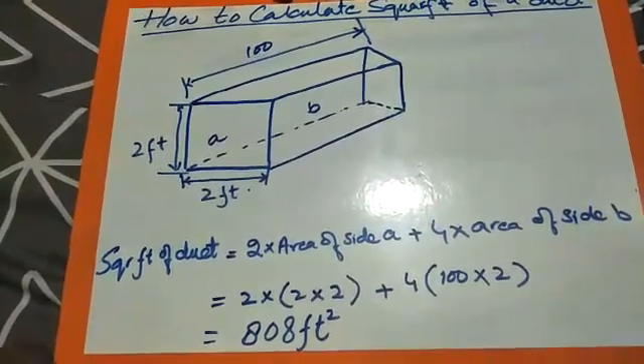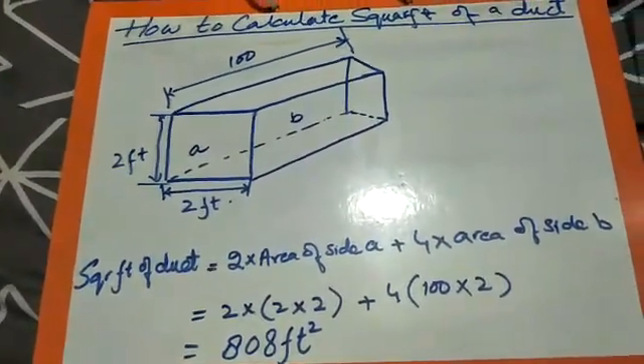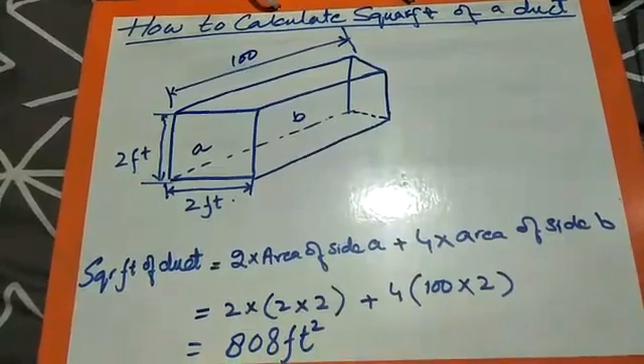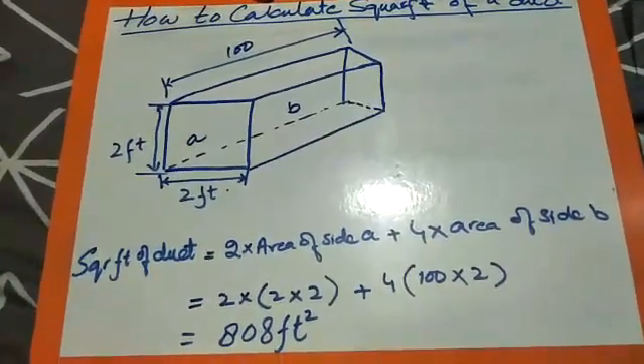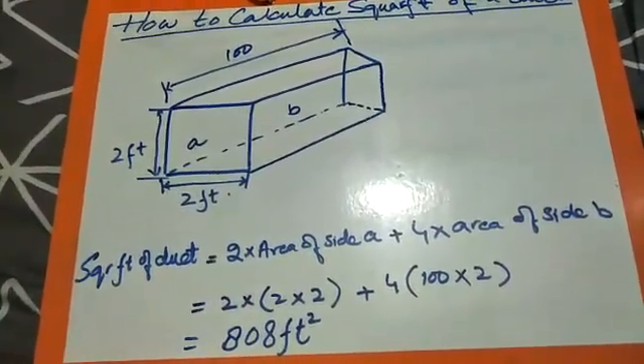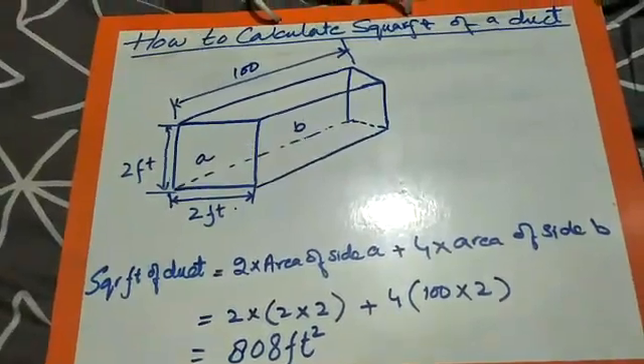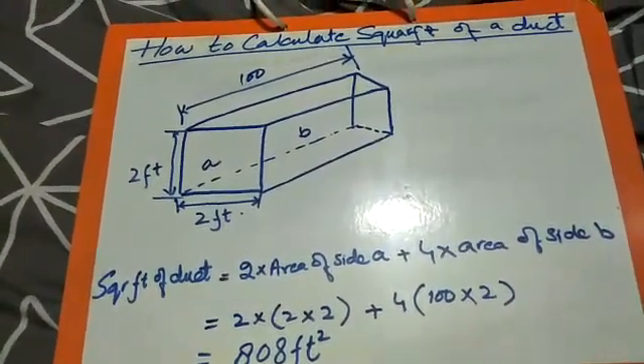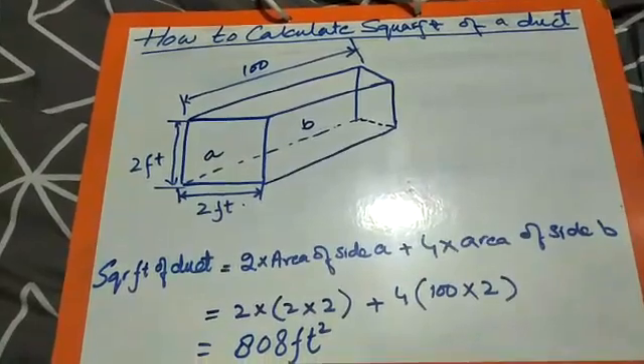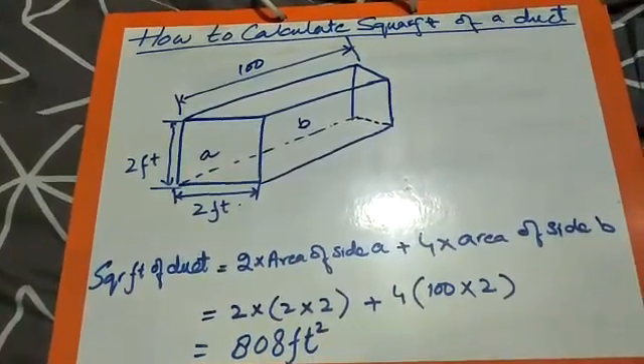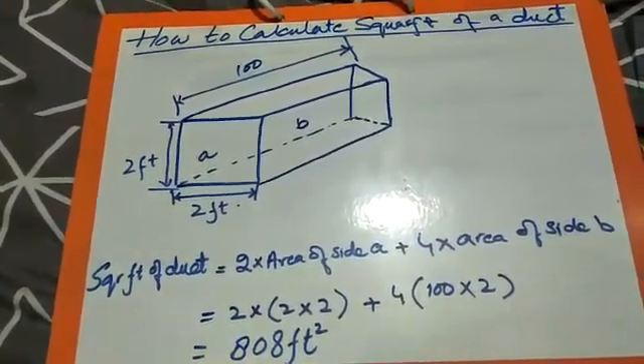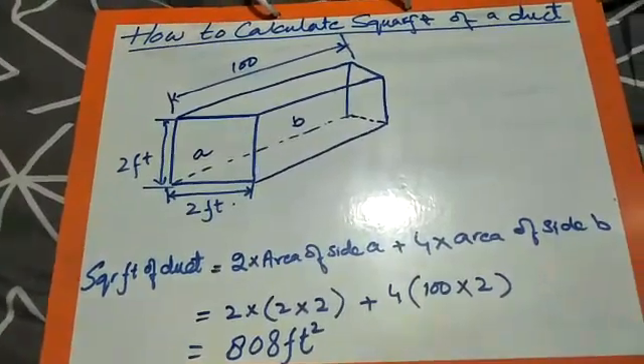Now for side B, in this duct there are four sides of equal size: front of B, back of B, top of B, and bottom of B. So the square foot of duct will be equal to 2 multiplied by area of side A plus 4 multiplied by area of side B.